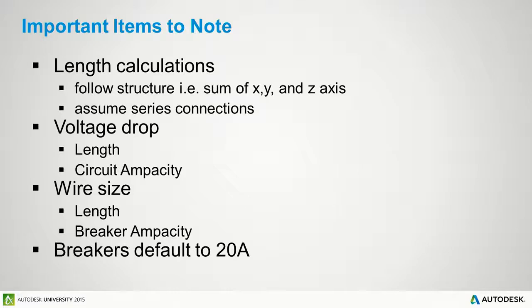There are settings at the beginning of the MEP settings where you define for certain ampacities this wire size should be used. Default out of the box, they're pretty good. I think there's one that might be slightly off, and it's a difference between 75-degree and 60-degree wire sizes. And some engineering firms choose that 75-degree across the board is acceptable because you've met the criteria that NEC says. So as a whole, it's fairly accurate for that.